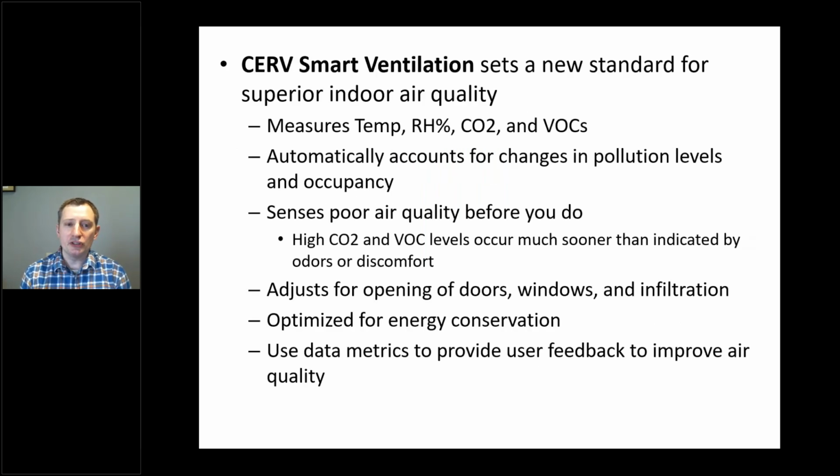Now with the CERV smart ventilation, we measure temperature, relative humidity, CO2, and VOC levels, and then we can automatically make changes in the operation based on these readings as well as the set points. While you may associate being able to smell pollutants with determining when you may need ventilation, the sensors built into the CERV, the independent CO2 and VOC sensors, are highly sensitive and will pick pollutant levels up much sooner than you should be able to detect just by odors or comfort levels.